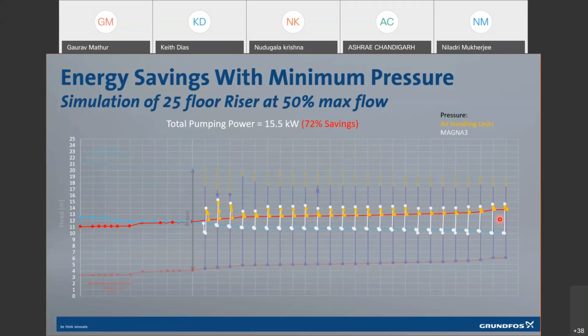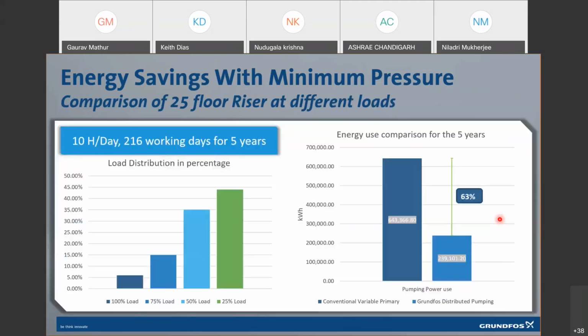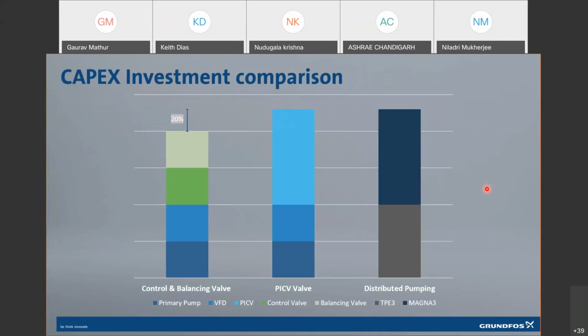And this actually makes the system much more efficient because here you are not building the pressure and killing it. You are only generating the pressure which is required to overcome the friction loss. If we look at the overall profile for a period of 5 years, we are able to see, from a baseline pumping to a distributed pumping, a saving of around 63% over a period of time.